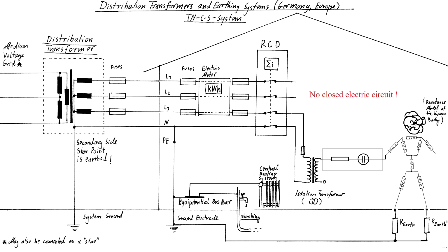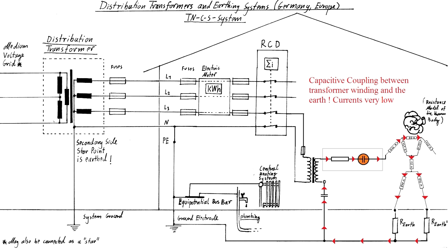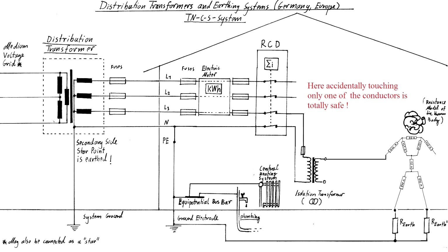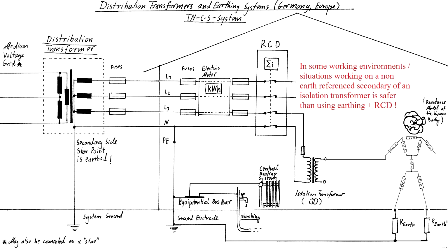Should the lamp light up nonetheless, even though there is no measurable resistive path to earth ground, the reason is the capacitive coupling between the windings and earth. While that capacity might be high enough to light the lamp, no dangerously high currents will flow, even if you touch one of the secondary ends directly. That's basically the main advantage of an isolated system in comparison to an earth reference system with RCD. In some working environments and situations, this and other secondary advantages of the isolation transformer are the reason why it is recommended or even mandatory for some applications.